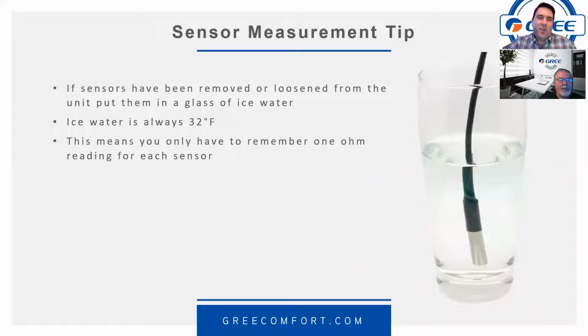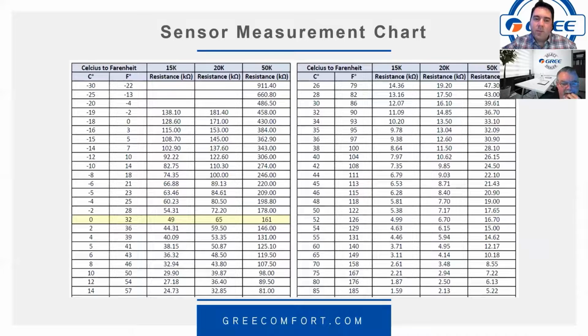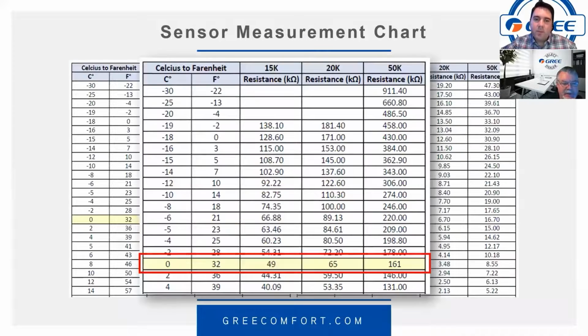Yep. So, one thing we thought of for sensor measurements: if you can get a glass of ice water to the end of that sensor lead, ice water is always 32 degrees. So now you don't have to worry about having your temperature chart. You only have to remember 3 values, right? Because if you're always testing at 32 degrees, now I only need to remember 49 for a 15K, 65, and 161 for a 50. That way, it doesn't matter what the ambient temperature is. You're always going to be accurate.